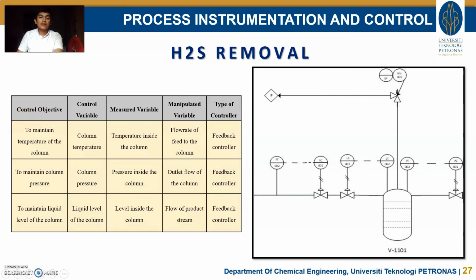And the second last equipment is H2S remover. There are also 3 control objectives. The first one is to maintain temperature of the column, to maintain column pressure, and the last one is to maintain liquid level of the column. The measure variable for the first one is temperature inside the column, which the manipulated variable is flow rate of feed to the column. The second one, the measure variable is pressure inside the column, the manipulated variable of outlet flow of the column.